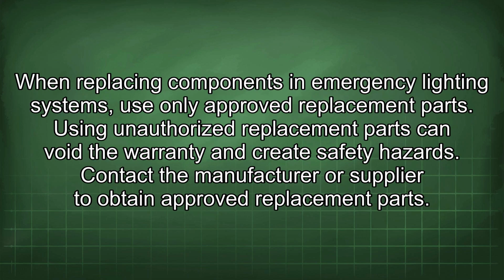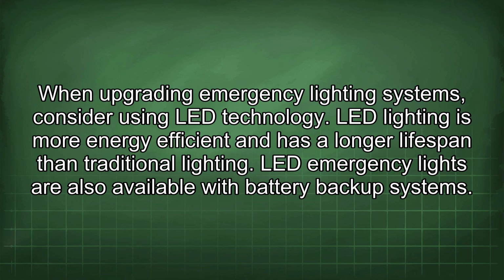When replacing components in emergency lighting systems, use only approved replacement parts. Using unauthorized replacement parts can void the warranty and create safety hazards. Contact the manufacturer or supplier to obtain approved replacement parts. When upgrading emergency lighting systems, consider using LED technology. LED lighting is more energy efficient and has a longer lifespan than traditional lighting. LED emergency lights are also available with battery backup systems.